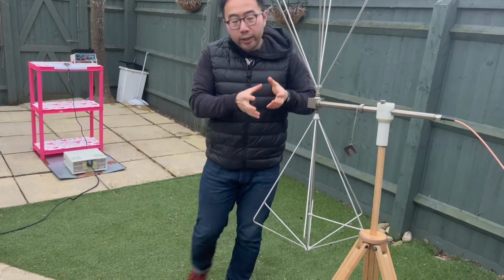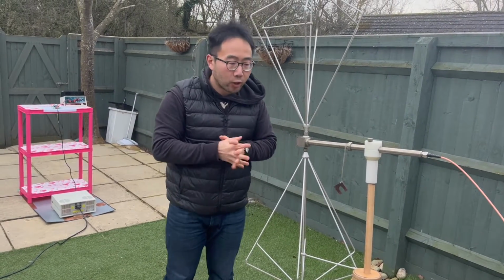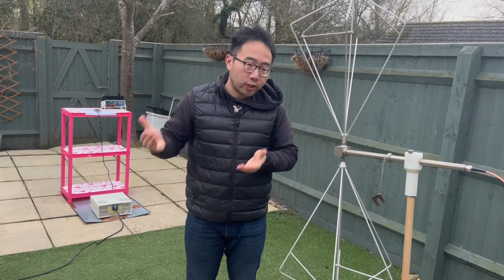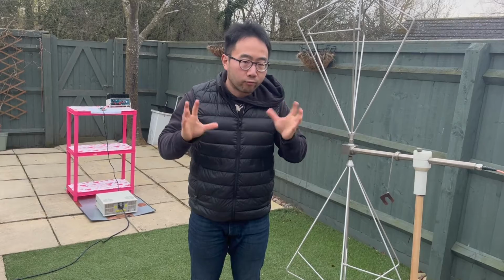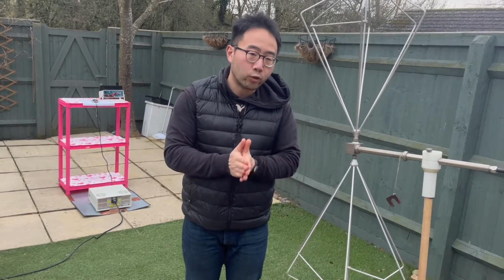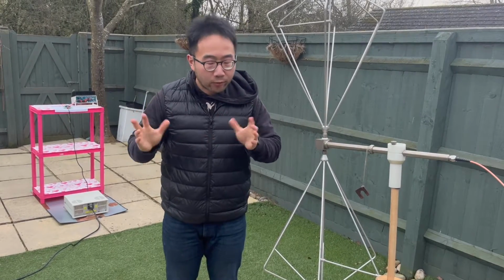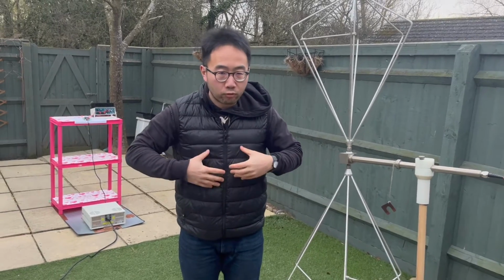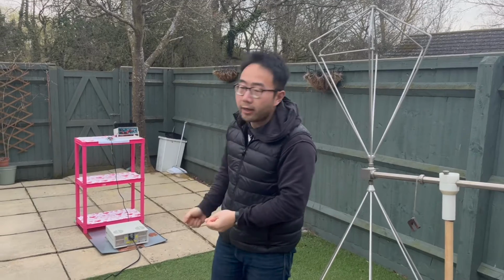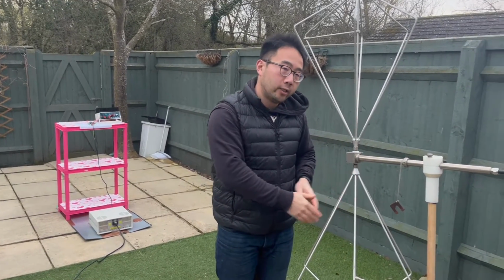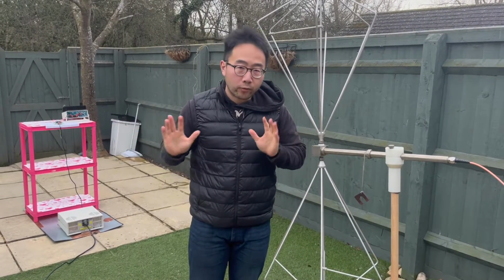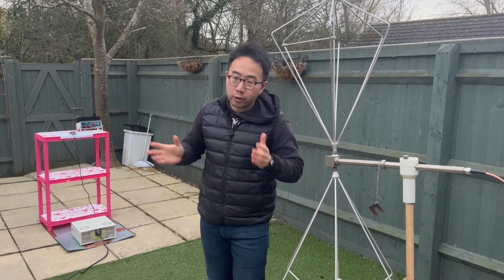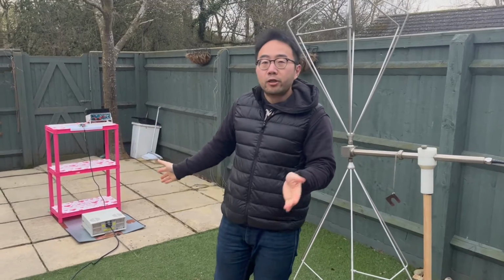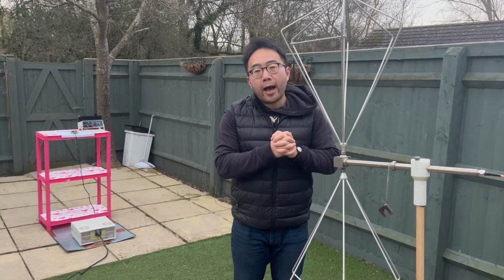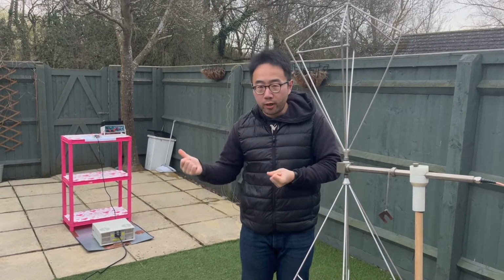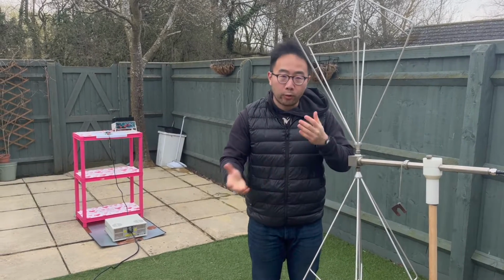And in this case, we're only doing the measurements using the full-size biconical antenna, simply because as we checked the EM performance of the DUT in a TEM cell, the red flag area where in the frequency range where this DUT radiates the most is often between 30 megahertz to about 300 megahertz. And because it is a power converter, the main radiated mechanism is actually through the mains cable. So in that case, a full-size biconical antenna, which often works between 30 megahertz all the way up to about 300 and 400 megahertz, is the ideal choice for measuring radiated emission. So in this case, we're going to perform a 3-meter distance scan, but first we're going to do an ambient scan, and then we're going to power the unit up and do the scanning while the unit is powered up, and we're going to compare the performance.